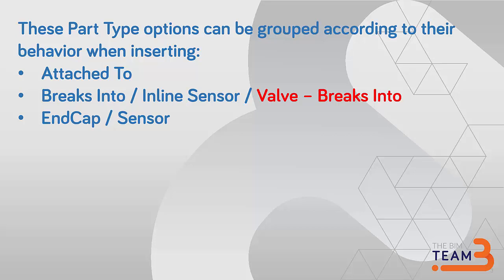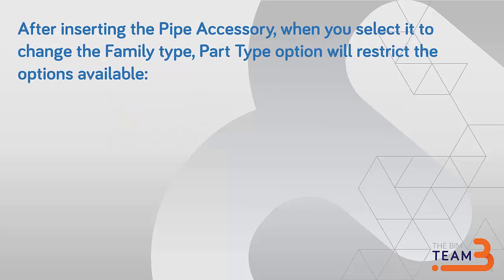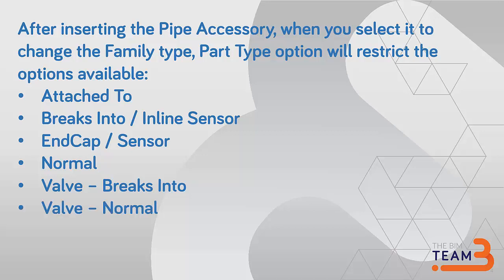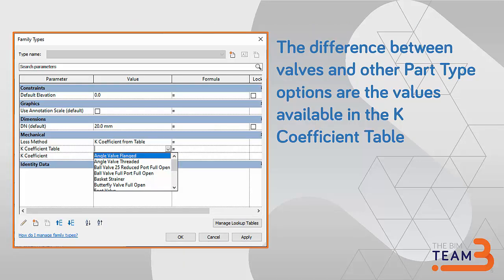The way to create a family is exactly the same within each of these groups, and normal and valve normal are the fourth type. After you insert the family in the project, when you select and want to change the part type, they will be grouped in six different sets: attach-to, breaks-into, inline sensor, end cap and sensor, normal, valve breaks-into, and valve normal. So if you insert one family that's breaks-into, you can exchange it with an inline sensor but not with a valve breaks-into. Another difference when you have valves versus other parts is that in the K-coefficient table you have many more options.